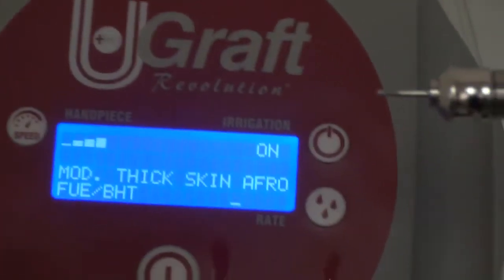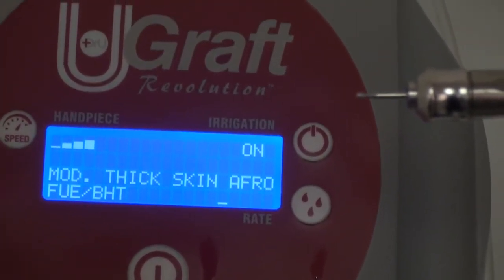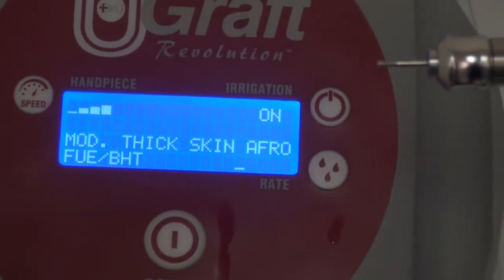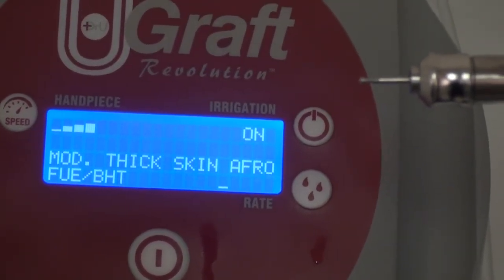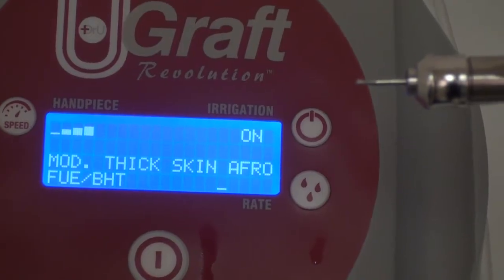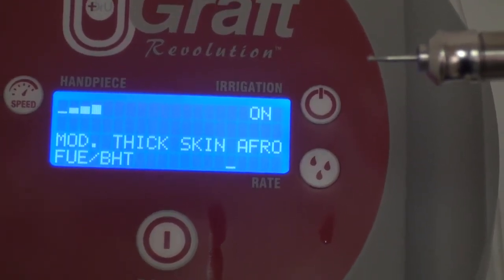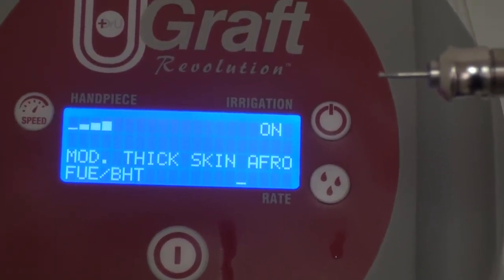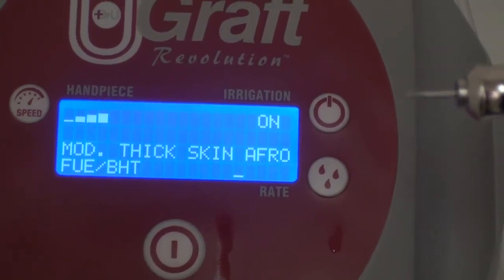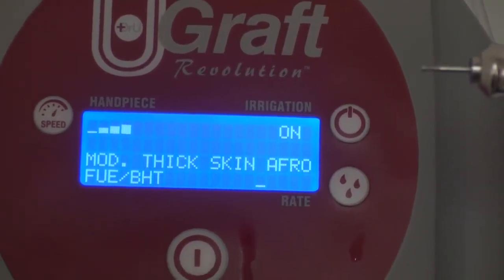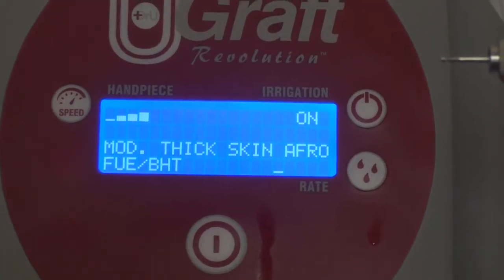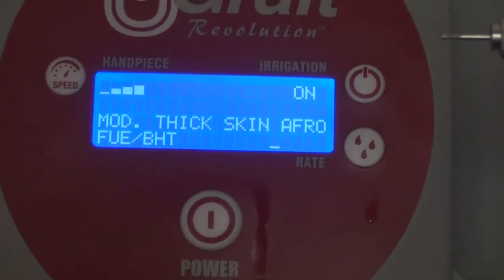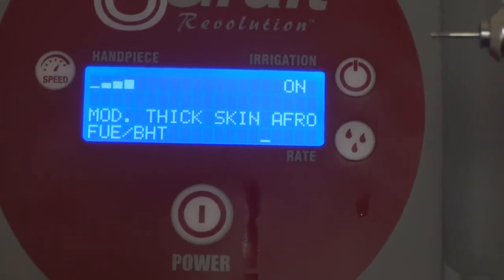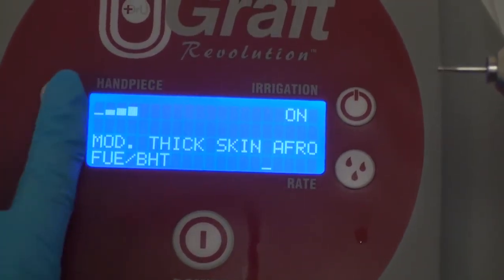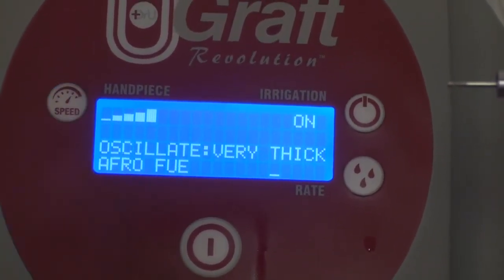The fourth setting, which is the one we are showing now, is the highest setting for the revolution mode. At this point, all skin types would be penetrated. You would succeed in penetrating even the toughest afro hair skin patients with the fourth setting. However, if using the fourth setting you are able to penetrate the skin but getting a lot of damaged grafts or transection, it is time to move to the fifth setting, which is the oscillation mode.